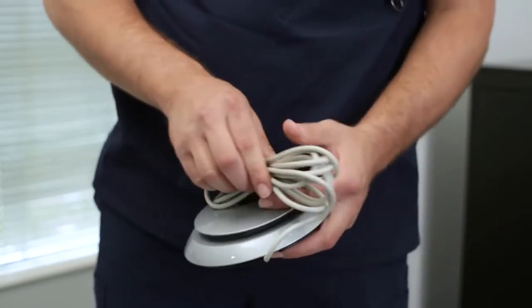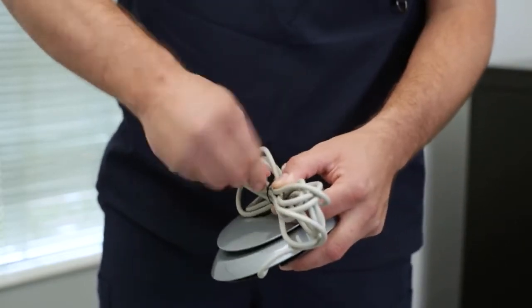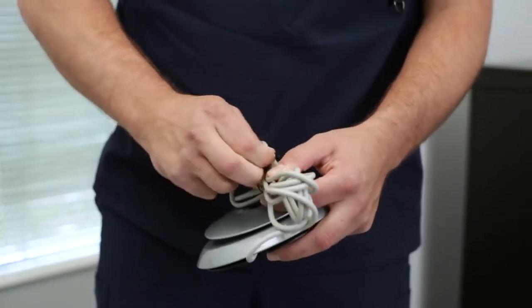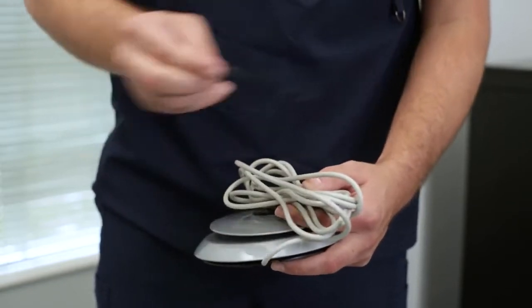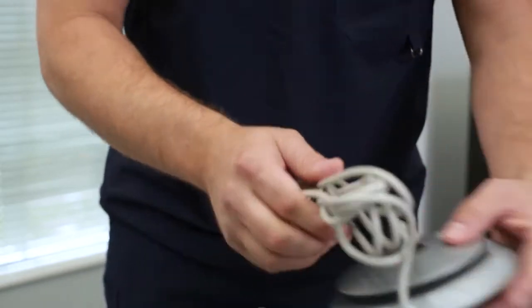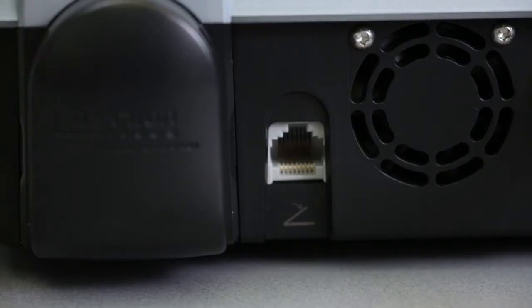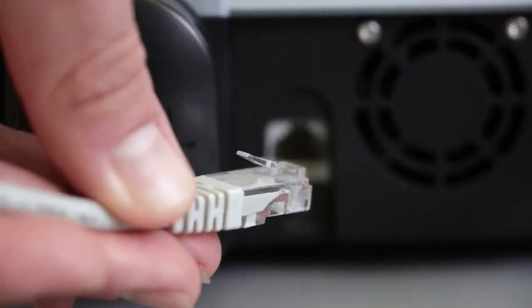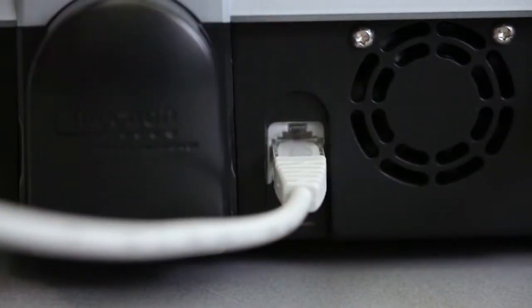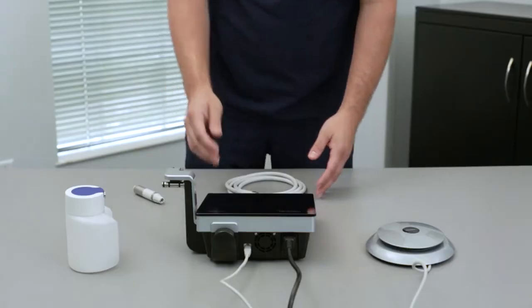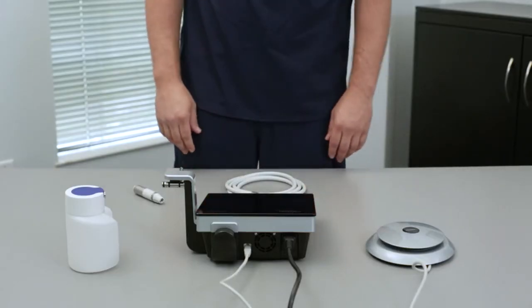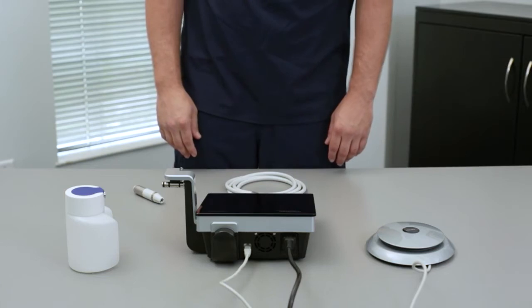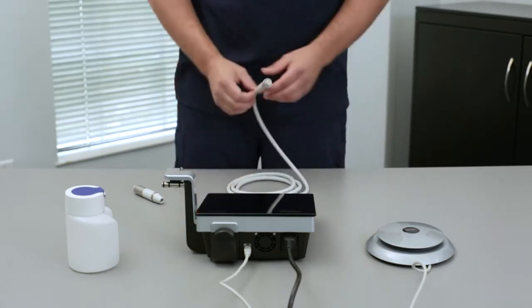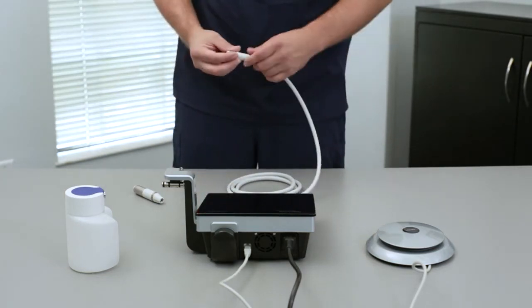Second, take the foot pedal out of the plastic bag and remove the twist tie from the cord. The port for the foot pedal connection is to the left of the power cord portal on the back of the device console. It will look like a Category 5 or Ethernet connection. Be careful not to break the plastic tab off of the foot pedal connector. Insert the connector into the port, then turn the device console around so that you are facing the front and top of the device.